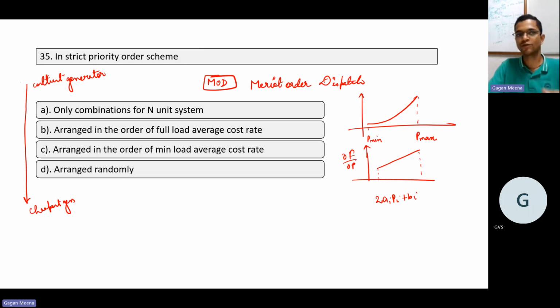That is used to perform this kind of dispatch. If the demand is minimum, they will use the cheaper generators. As the demand increases, they will keep on adding, because they have that stack available with them, showing which generator is the costliest and which one is the cheapest. It's easily available online for Maharashtra. I have one of those; you can see it for Maharashtra.